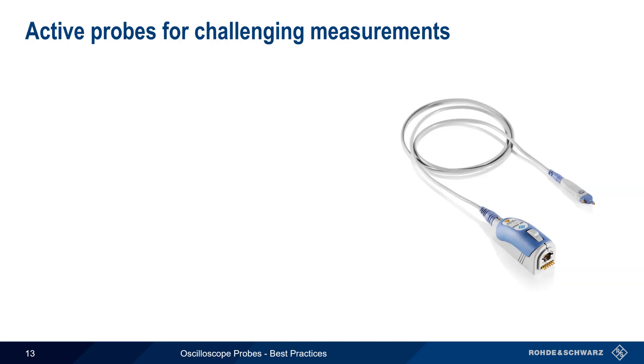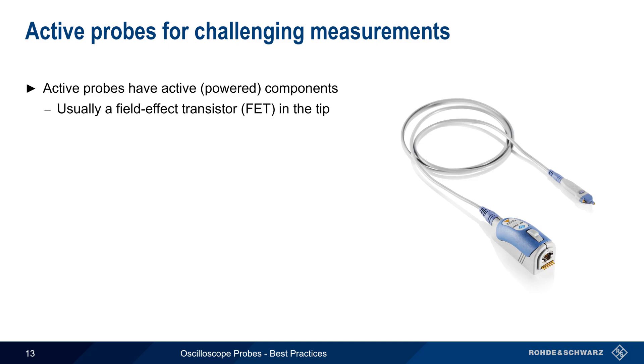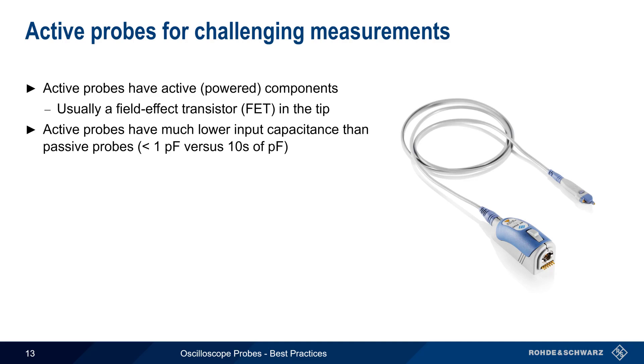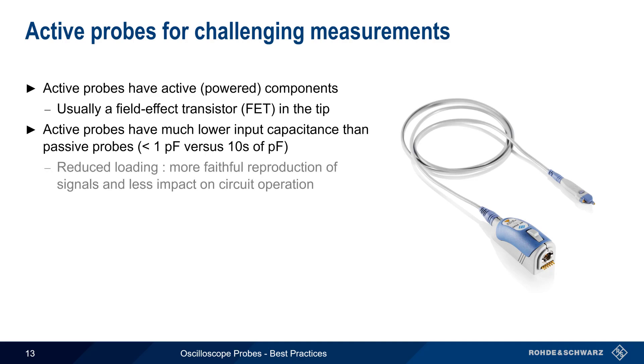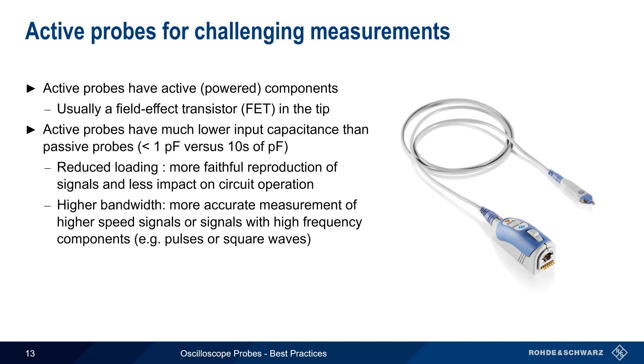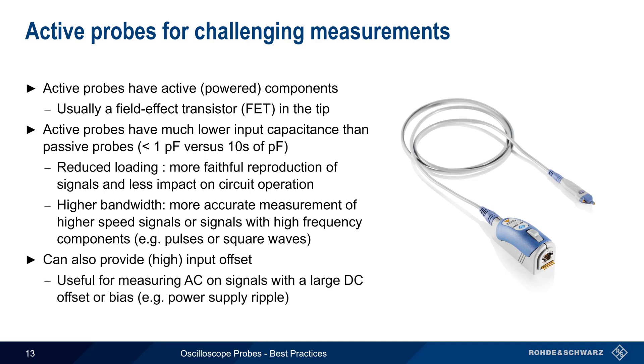Our last probing tip is when to use active probes. As the name implies, active probes have powered components — in this case, a field effect transistor, or FET, in the probe tip. Active probes have much lower input capacitance than passive probes — usually a picofarad or less, compared to tens of picofarads for passive probes. This lower capacitance has two major advantages: reduced circuit loading, which allows for a more faithful reproduction of the measured signal and a lower impact on circuit operation; and higher bandwidth, which is needed for more accurate measurement of higher speed signals and signals with high-frequency components such as square or pulsed waves. In addition, some active probes can apply a relatively large offset to the signal, which is very useful when measuring small AC signals on top of large DC signals, such as power supply ripple. Active probes are therefore an excellent choice for demanding measurement applications.